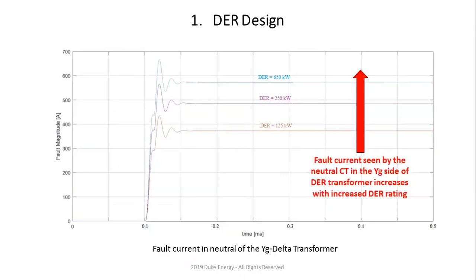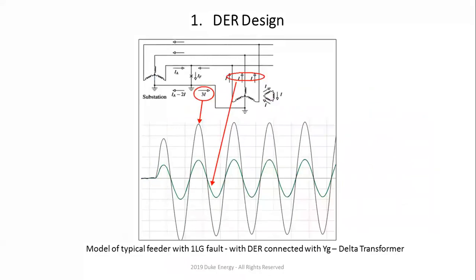So essentially what happens is that the Y grounded delta transformer becomes a source of zero sequence current. So now the fault current that's seen by the neutral CT, which is literally between the ground and neutral of that Y grounded delta transformer tied to the PV, increases, right? And why is that so? Well, if you see this particular screen over here, a much simpler presentation, we have a fault current somewhere in the middle, and with the Y grounded delta transformer, that now becomes a source of zero sequence current. So the fault current that should go all the way to the left over to the substation now splits. And that is not good because the relay settings in this case are desensitized. So what that means is that you will not be able to see the fault for some particular size of the PV.